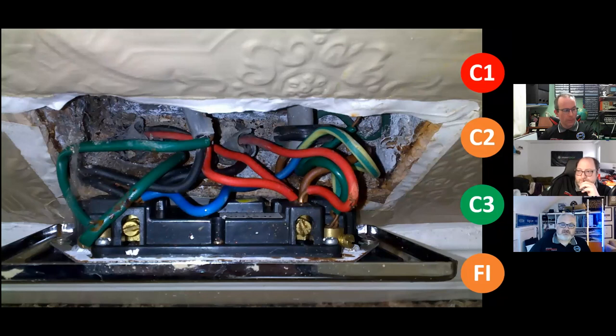You know, that socket's designed for a certain loading. The cables in that circuit will be under far greater load if you've got the entire ring final, you know, 30 amps flowing through the back of it. That could put strain upon the conductor, on the connection, on the plastics around it. I just think it's a bodge which could give rise to danger. So I think it's a C3FI, but it could easily be a C2FI as well if you were going to tie it into the hierarchy of Electricity at Work Regulations, which an electrician in a domestic home, if you're employed by a contractor, you are privy to. Don't think you're exempt.